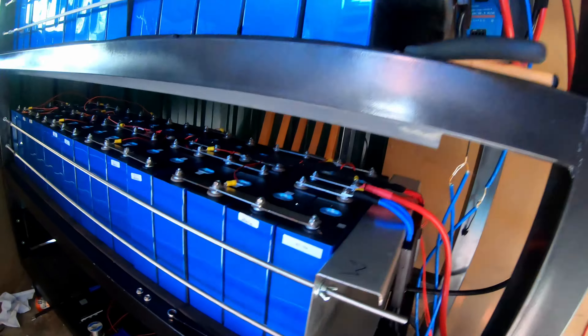Functionality is probably more important than making it look pretty. We've created more mess by doing what we've done today, so I've got to clean that up and then push this back. I've got to move the other MPPT up into the corner. It's getting heavy to move — it's essentially 90 kilowatts all on the rack, ready to go. We've already turned it on. Actually, what I should say is we didn't turn it off, but I've adjusted the Victron now. It's got 1,800 amp hours of lithium batteries.